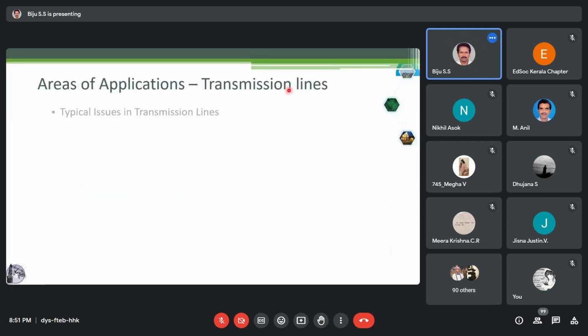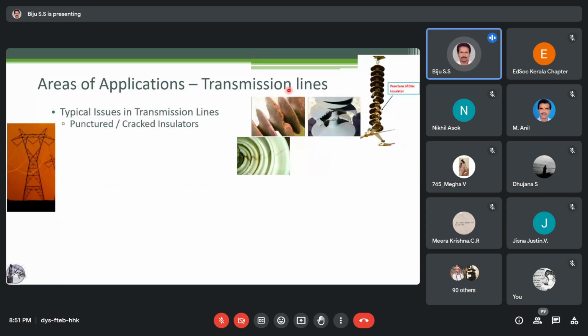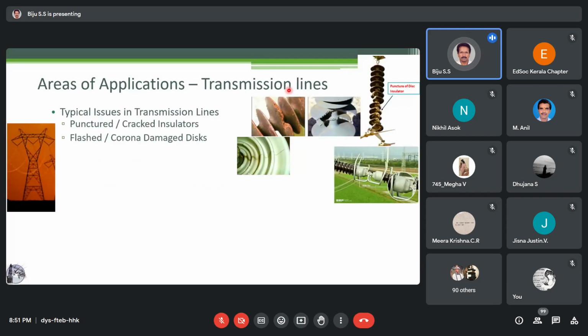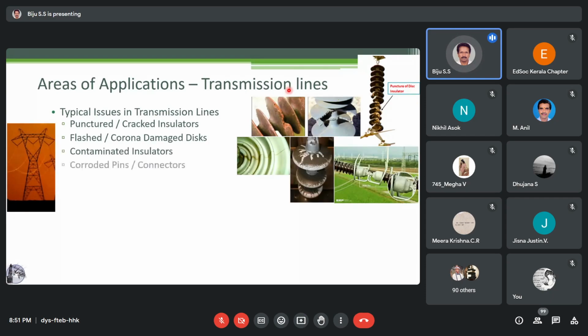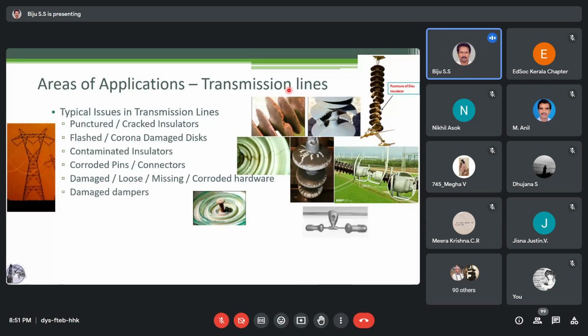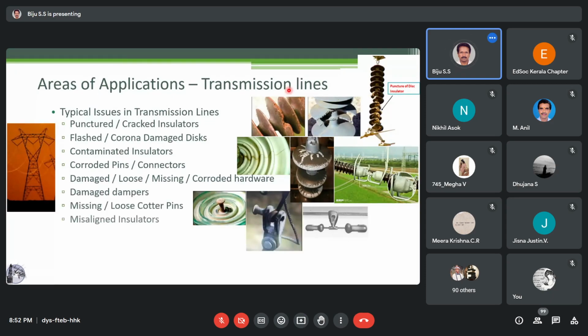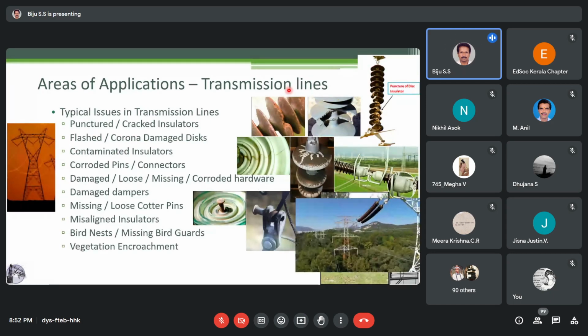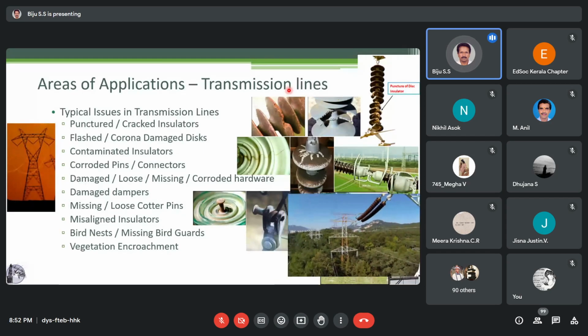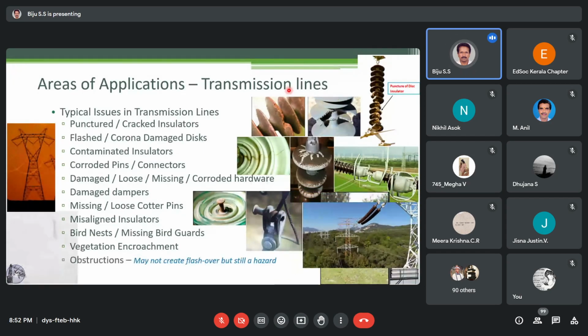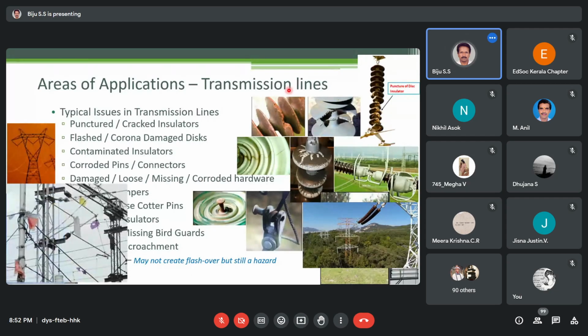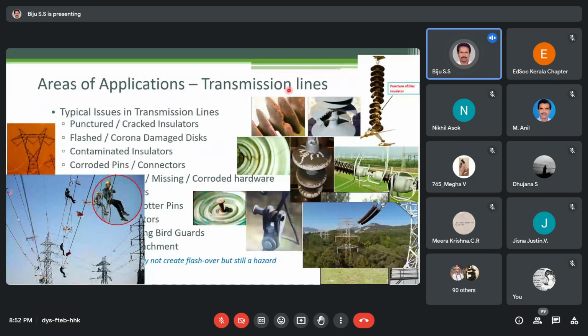Move forward. There are various applications. Punctured and cracked insulators can be identified, flashed discs can be identified, contaminated insulators can be identified, corroded pins or connectors can be identified, and damaged, loose or missing hardware can be identified. Also damaged dampers, missing pins, bird nests, and vegetation encroachment. All these things can be identified through AI logic algorithms. Obstructions can be identified or removed. Okay, there are a few reels on that.